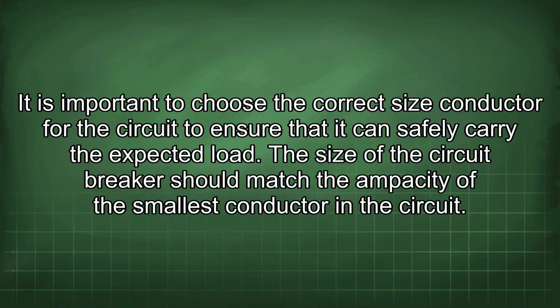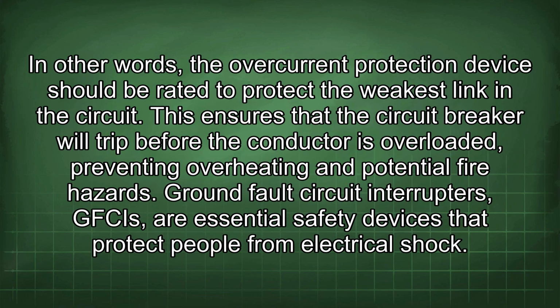It is important to choose the correct size conductor for the circuit to ensure that it can safely carry the expected load. The size of the circuit breaker should match the ampacity of the smallest conductor in the circuit. In other words, the overcurrent protection device should be rated to protect the weakest link in the circuit. This ensures that the circuit breaker will trip before the conductor is overloaded, preventing overheating and potential fire hazards.